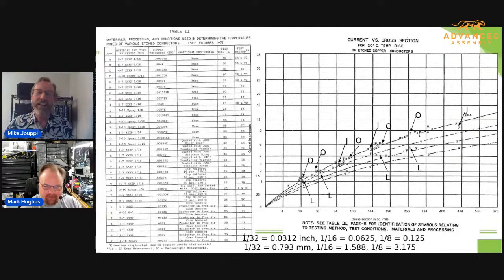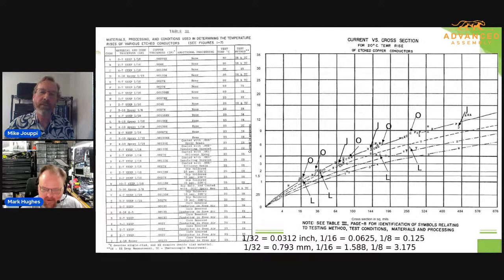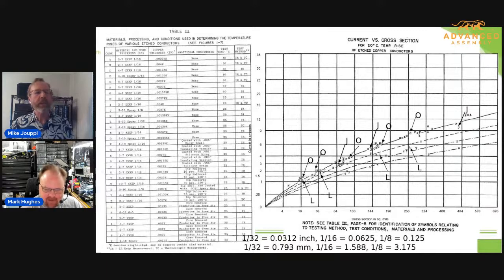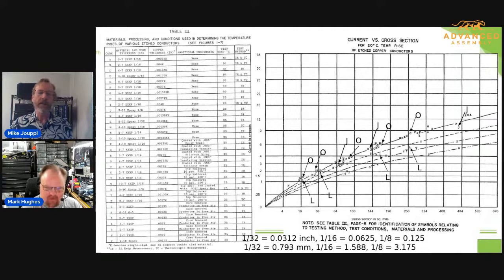So that's going back to this chart, and that bottom curve there — on the left-hand side in that table there's a note that says 'removed from core.' That's what they meant: they removed it from the board and tested it just in air. I think what they were concerned about is that if the trace had lifted off the board, what would its temperature be? They wanted to get an idea — had a trace lifted. They were having a hard time adhering to the board materials back then. And so by knowing what kind of limits you have, that was the intention.